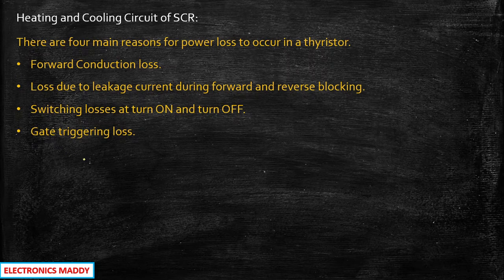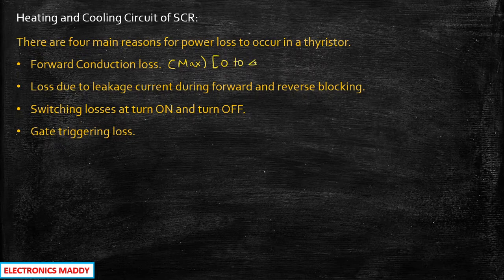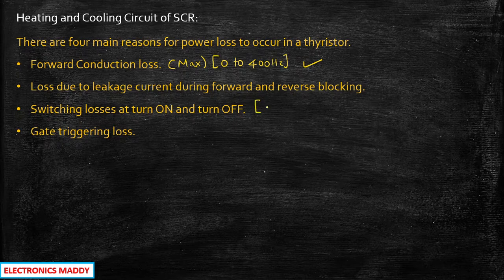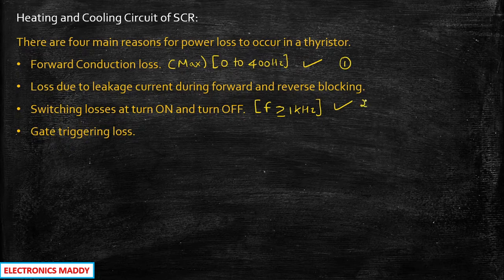The forward conduction loss is the loss that has the maximum value during operation, occurring at frequencies in the range of 0 to 400 Hz. In industrial applications, forward conduction losses are maximum, so this loss is very important and needs to be taken into consideration. When talking about frequencies much greater than 1 kHz, the switching losses will also go high. So we have two important losses to consider: forward conduction loss and switching loss for higher frequency ranges.